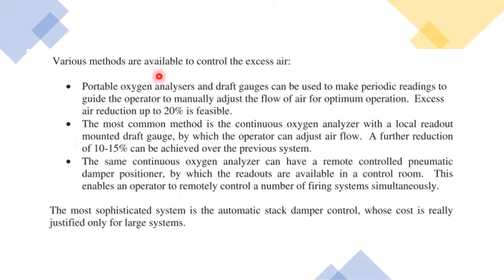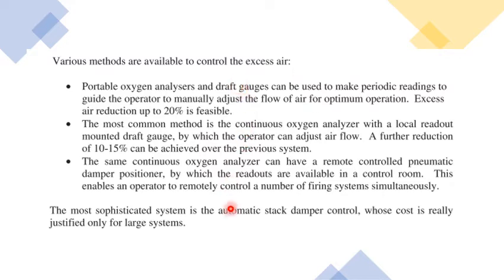Different methods are available to control excess air. Portable flue gas analyzers and draft pressure gauges can be used to make periodic readings to guide the operator to manually adjust the flow of air. These instruments allow analysis of how much excess air is entering the boiler, enabling corrective actions to be taken for optimum operation and improved boiler efficiency.